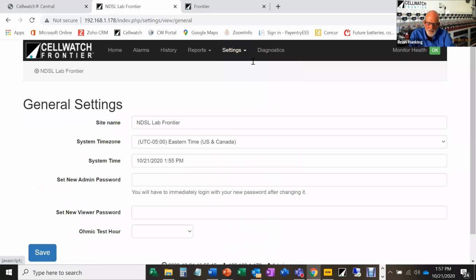Then we go to settings. You can see there's a whole lot of settings, but I'm not going to go through all of these. Battery design and battery profiles relate to a lot of these applications. Some are in an air-conditioned environment, which is great, but some are not, and a big temperature change, even a 10-degree change, can make a 10 or 20% difference in a measurement of this small nature. So what we have is a patented temperature compensation algorithm, where we profile the batteries we use for that kind of thing. It's not a general thing, but it is something we can do.